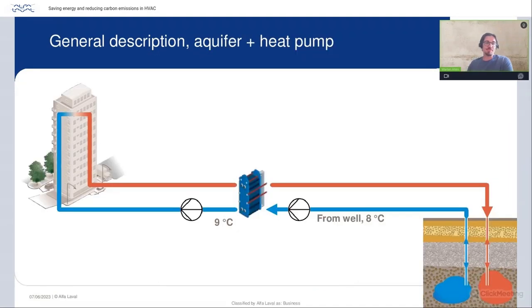That is what you can take for granted for an HVAC design on the market today, unfortunately. So if we work with an example, this is a building that is using aquifer storage for generating free cooling or a heat source for a building. You see here, we take from the wells or from the ground source 8 degrees, which is run through a heat exchanger to generate 9 degrees supply temperature to the building for the cooling loop. Then on the return loop, from the building to the heat exchanger, we get 14 degrees, which then turns into 13 degrees, which is re-injected down to the bedrock.